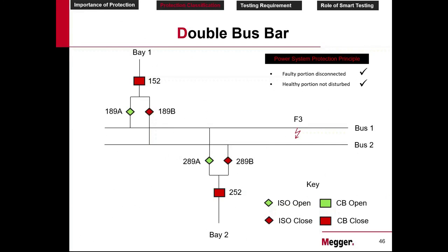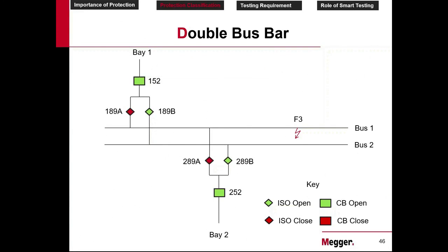Now, why do you need triple bus? That means there should be some drawback in the double bus. So the drawback is here. The second part, the healthy portion should not be disturbed. This is a question. Did we really do this? We can say the moment the fault occurred, just going back to the previous one, we tripped the breaker. That means you disturbed the healthy part.